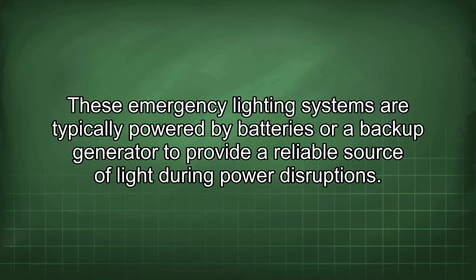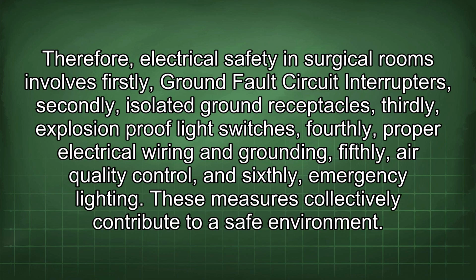during power disruptions. Therefore, electrical safety in surgical rooms involves firstly, ground fault circuit interrupters, secondly, isolated ground receptacles, thirdly, explosion-proof light switches, fourthly, proper electrical wiring and grounding, fifthly, air quality control, and sixthly, emergency lighting. These measures collectively contribute to a safe environment.